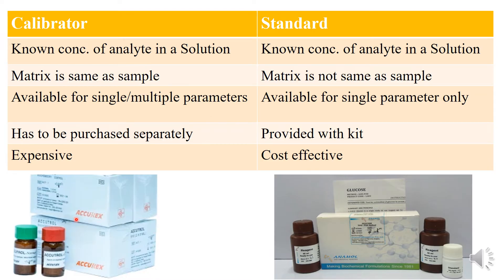Here you can see pictures of calibrators, and you can also see the standard vial available with a kit. Calibrators can cover different ranges — there are three levels: Cal1, Cal2, and Cal3 — covering the low, normal, and high range of any analyte that can be present in a patient sample. This makes the calibrator far more superior than the standard.